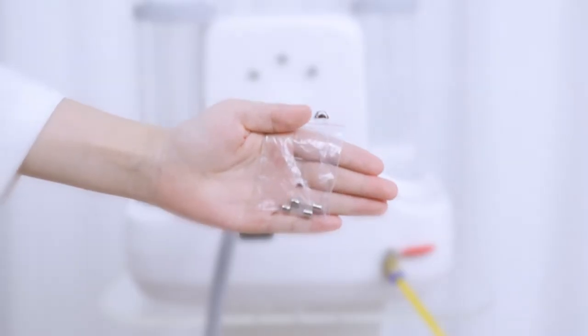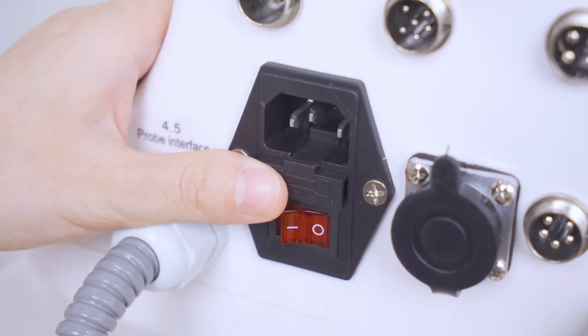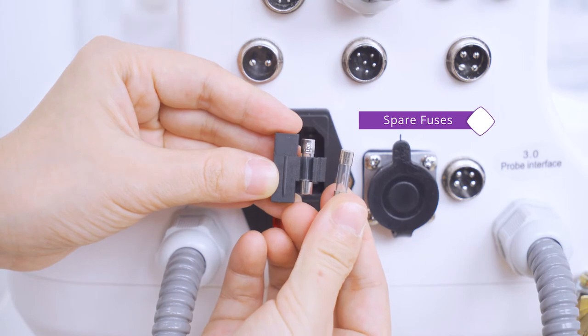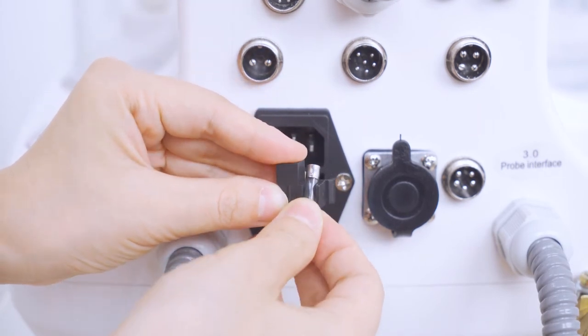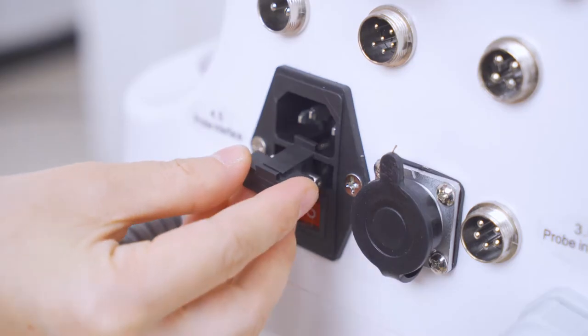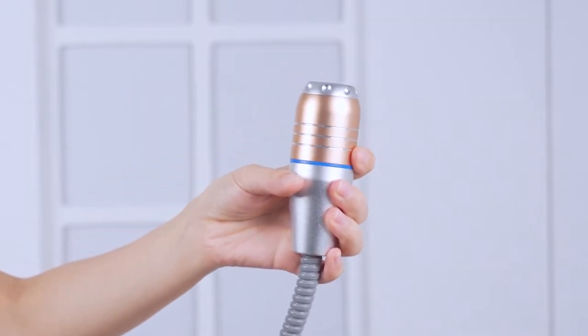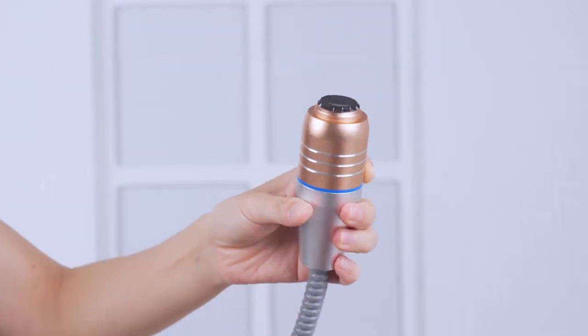Replace any faulty fuse with one of the two spare fuses. Pry open the fuse cover with the screwdriver, take out the faulty fuse and replace it with the spare fuse. Replace any faulty film with one of the two black protective films of the radar shaping probes.